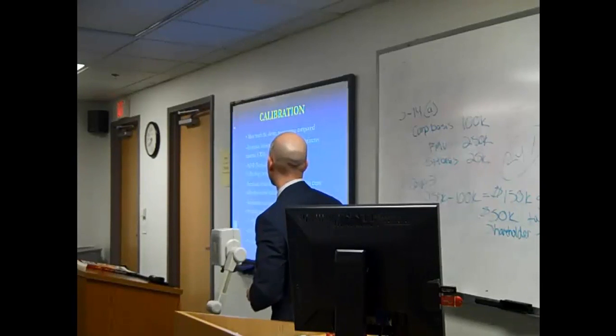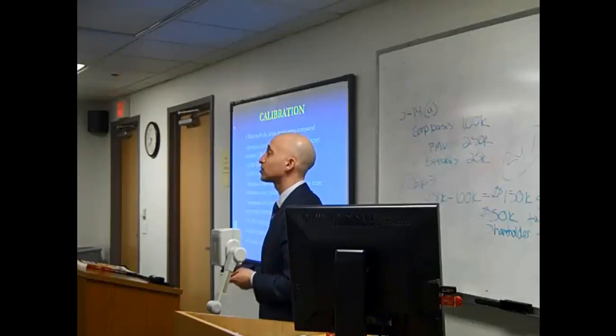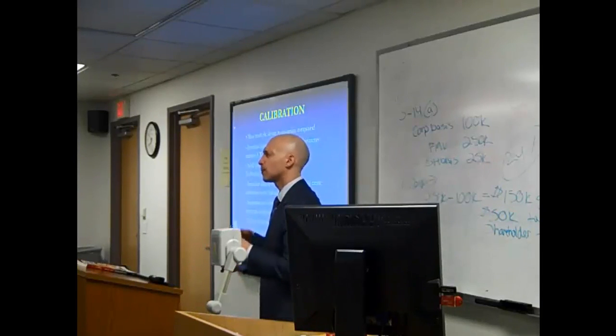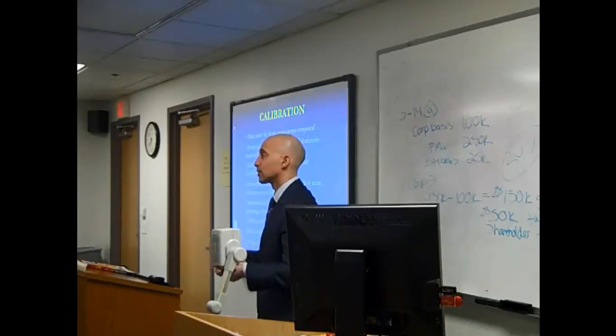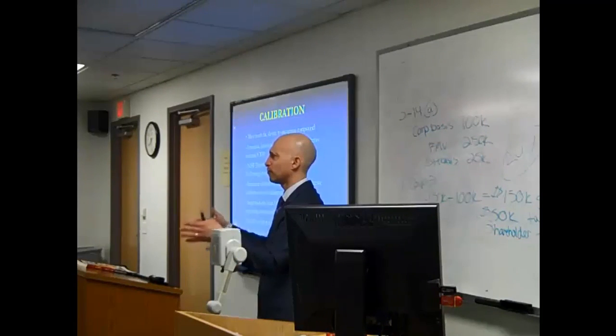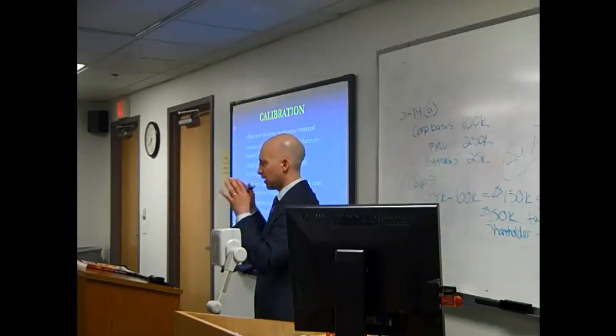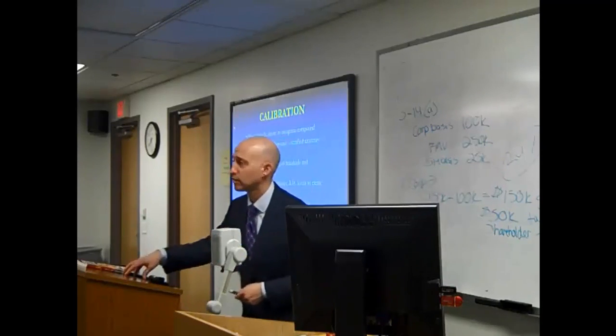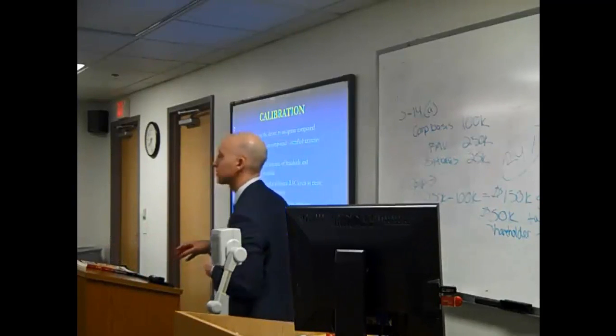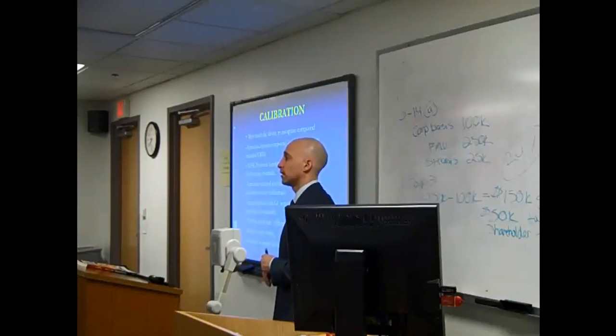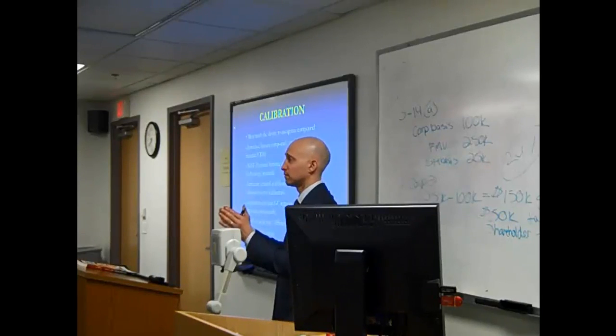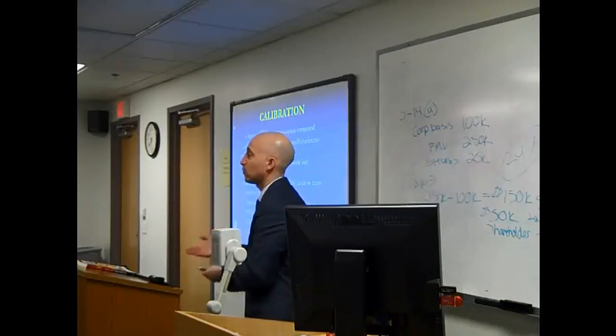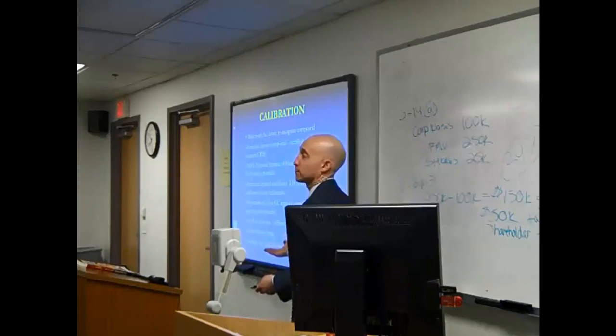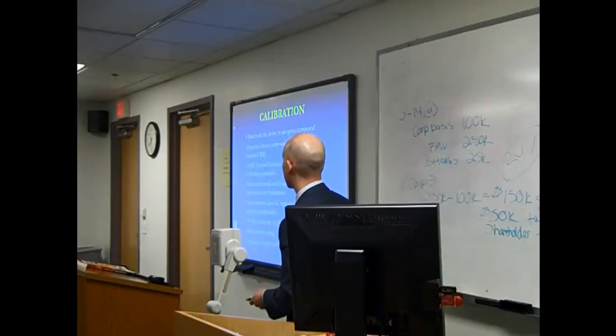Separation mix. There's something called a separation mix, which essentially is teaching the machine to also identify other compounds that are typically coming out in human blood. Maybe there's isopropanol, maybe there's methanol, acetaldehyde, okay? You have to teach that machine to be able to differentiate between all of those compounds. And again, you're introducing into that machine a standard, and you're teaching the machine, hey, this is what acetaldehyde looks like, this is what isopropanol looks like, and if there's proper separation, you're going to see the difference. Isopropanol is going to come out in 1 minute and 50 seconds. Acetaldehyde's 2 minutes, let's say, or 2 minutes 30 seconds, whatever the column does.